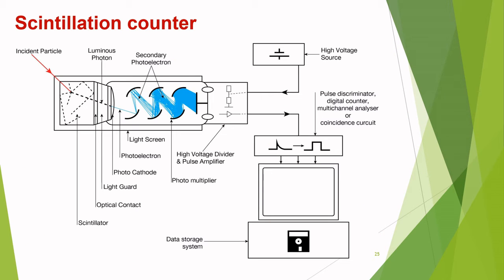This is the construction of the scintillation counter. It consists of a cell, a photomultiplier tube, which is coupled with a phosphor or fluorescent material to convert scintillations into electrical pulses, an amplifier and a scaler. For gamma radiations, as they have the most penetrating power, the phosphor used is a crystal of sodium iodide which is activated with about 1% of thallium for increasing the degree of fluorescence. The gamma radiation passing through a small window enters the crystal where it gives rise to a small flash of light. This is brought to the photomultiplier tube which in turn detects the flash, amplifies and converts it into an electrical impulse. This impulse may be recorded directly by means of a scaler.